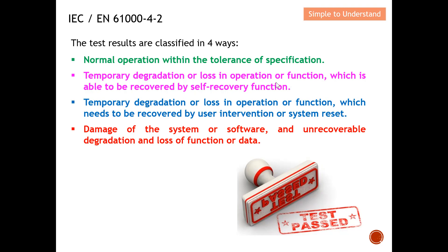Category three: temporary degradation or loss of function that requires recovery by user intervention or system reset — similar to category two but requiring manual action such as pressing reset. Category four: damage to the system or software that cannot be recovered, or loss of data — in this case the EUT is damaged and you will fail the test.